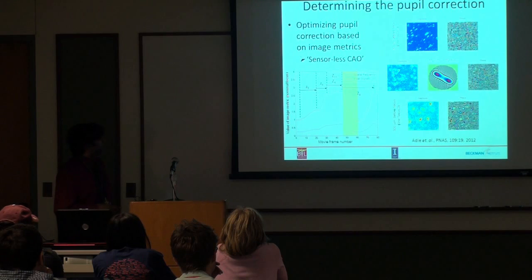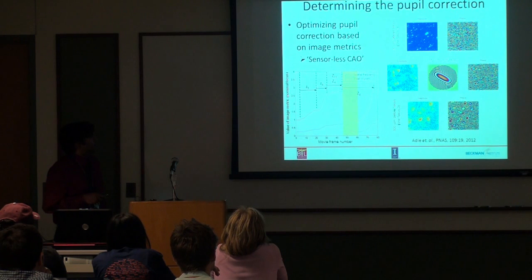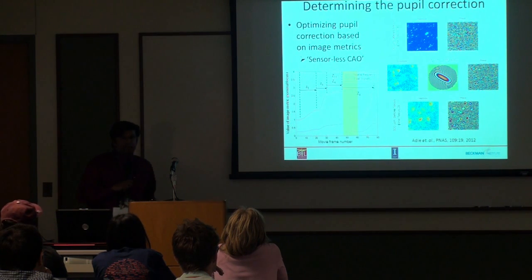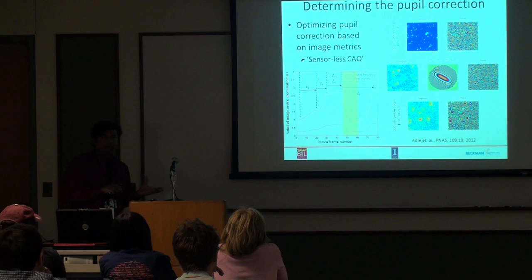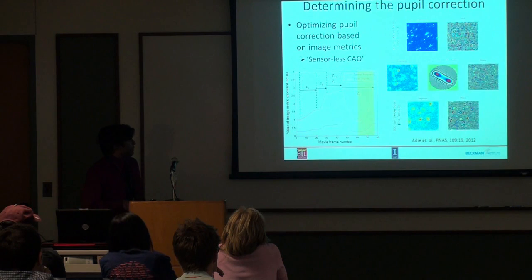Now in this step, let's shift the focus to the upper plane. The image metrics plummet because the plane of least confusion now has experienced defocus. But an important thing to note here is that this highlights a difference between refocusing and ISAM. A given value of defocus is optimal for a single plane only, whereas the ISAM resampling corrects defocus for all planes, all depths simultaneously. So finally, let's return the focus to the focal plane.